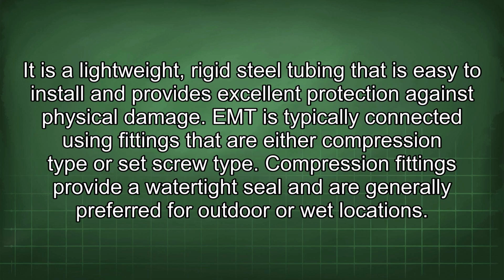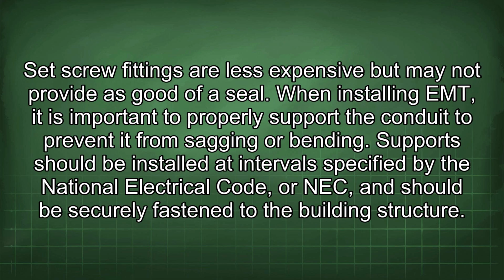Electrical metallic tubing, or EMT, is a common type of electrical conduit used to protect wiring in buildings. It is a lightweight, rigid steel tubing that is easy to install and provides excellent protection against physical damage. EMT is typically connected using fittings that are either compression type or set screw type. Compression fittings provide a watertight seal and are generally preferred for outdoor or wet locations. Set screw fittings are less expensive but may not provide as good of a seal.